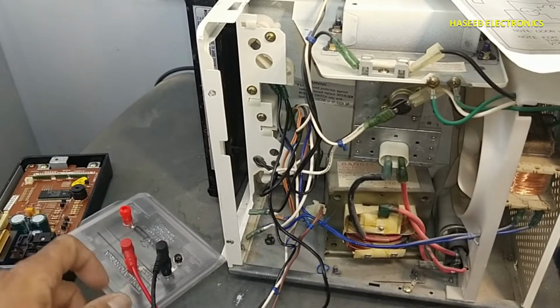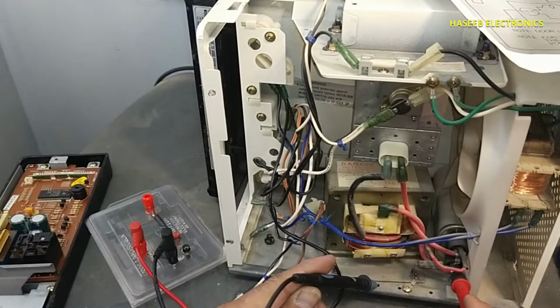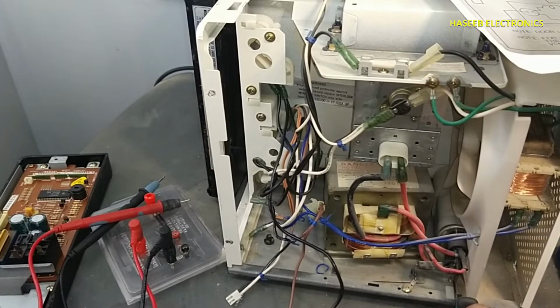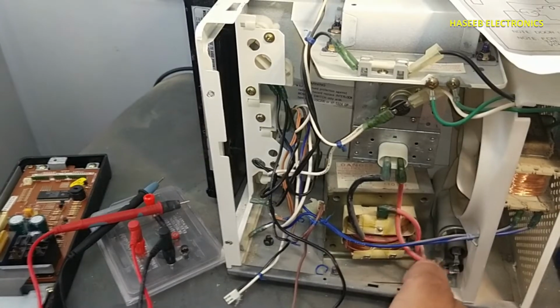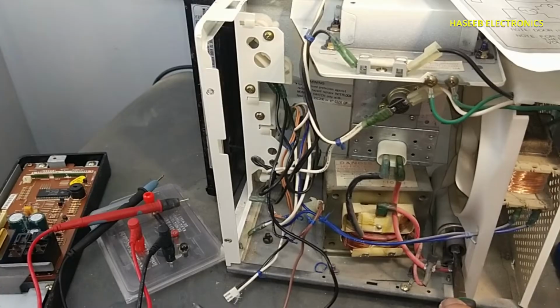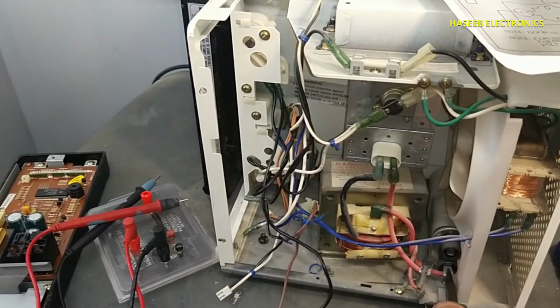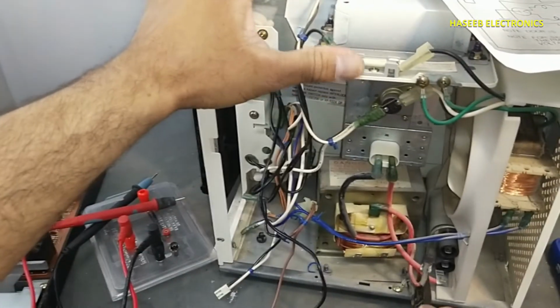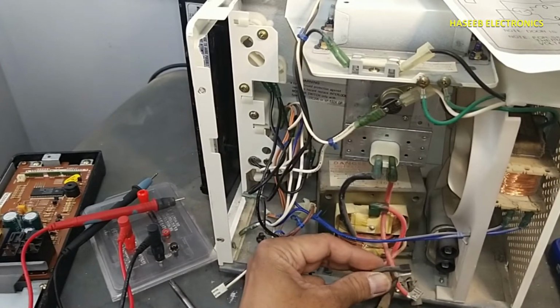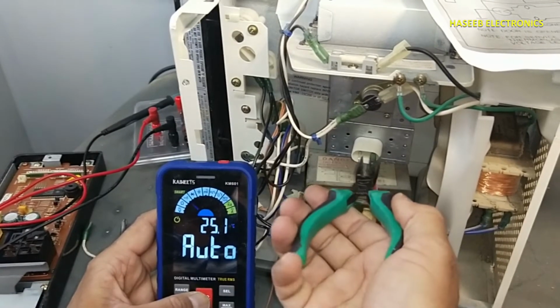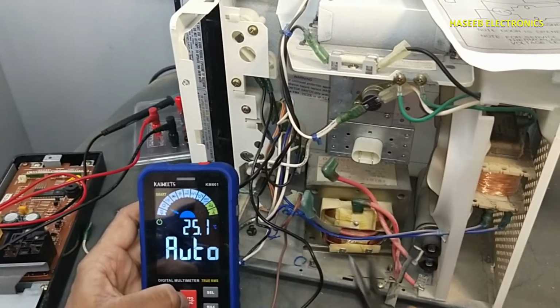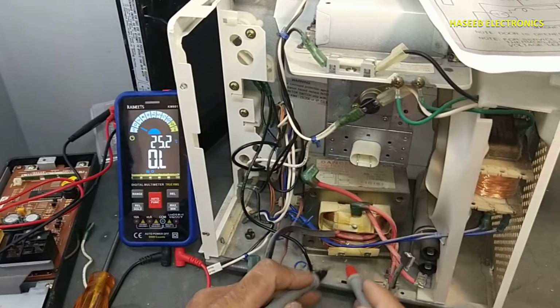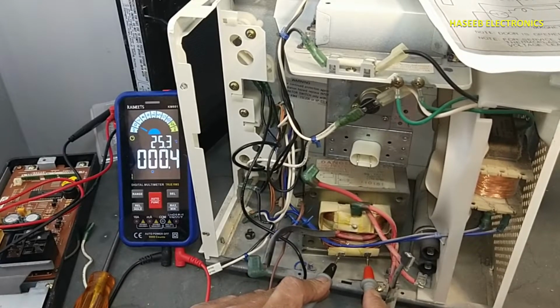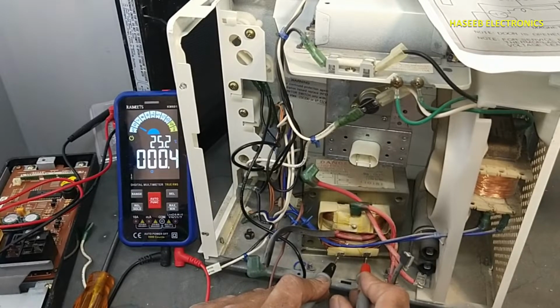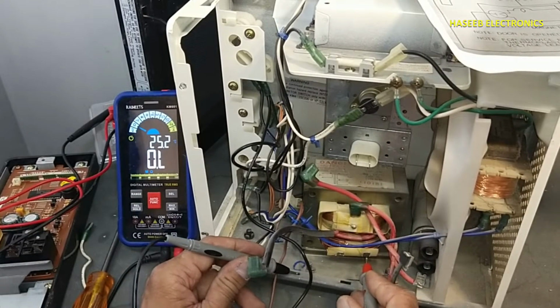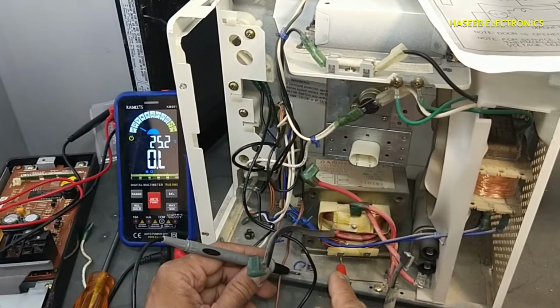Now we will check the high voltage transformer section. We will discharge it. For more surety, we will discharge with a plier. Now set the multimeter to resistance. In the transformer primary winding, it will give less than 1 ohm because it is a 110 volt transformer: 0.5, 0.4, 1 ohm, like that. Check between chassis, it must be open. It will not give any resistance between chassis.